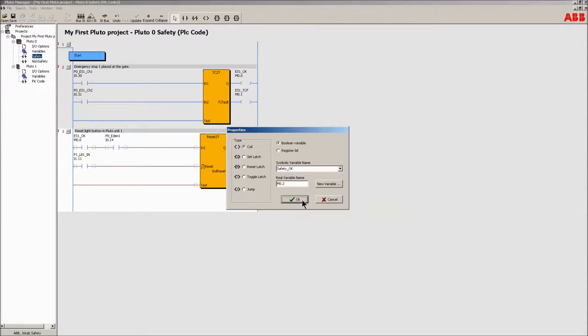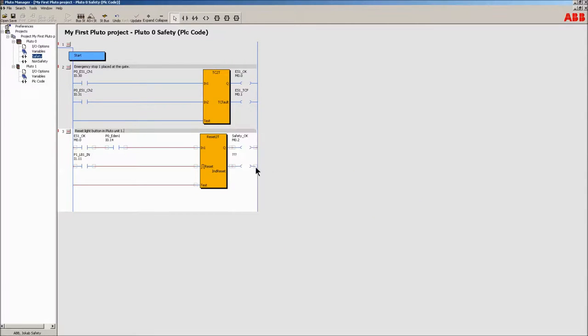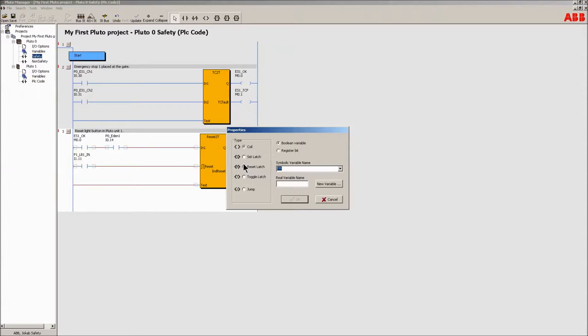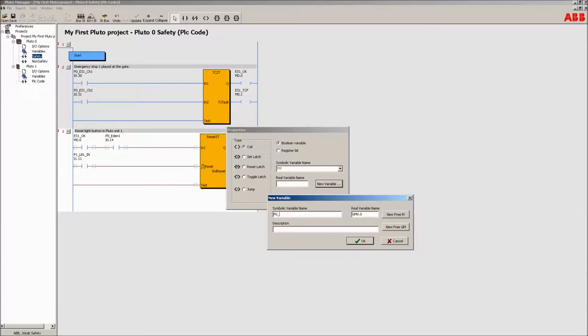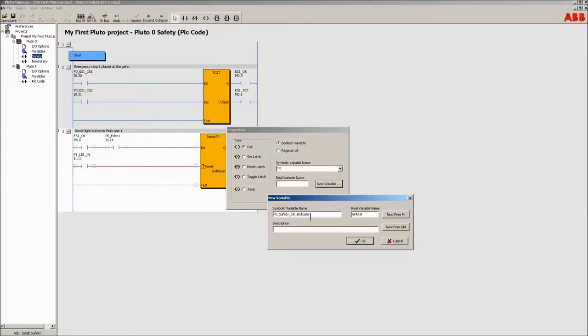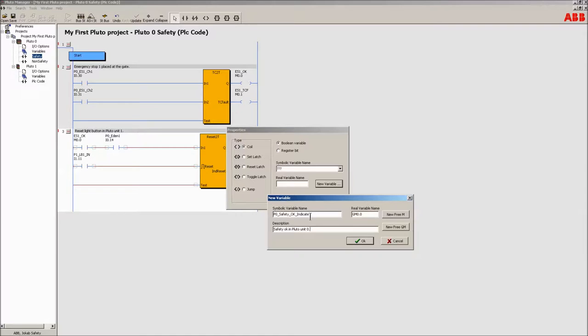Since the reset light button is in the other Pluto unit, unit 1, the status must be transmitted over the bus. Use the quick button and use a global memory instead of a local. Then its status will be transmitted over the bus between the two units. This will be used later to use the light button's indicator light to show the status of the safety in the machine.